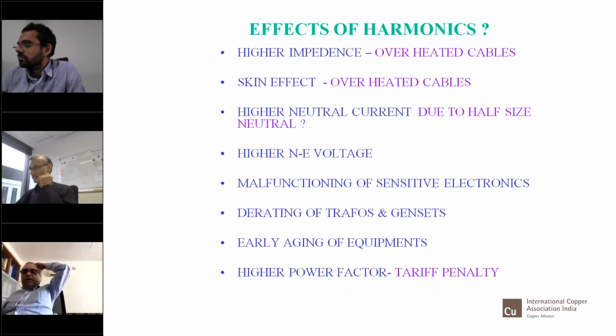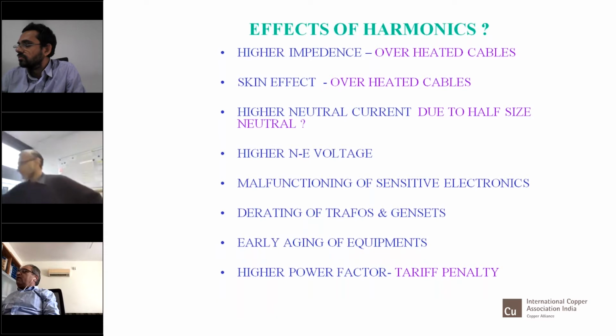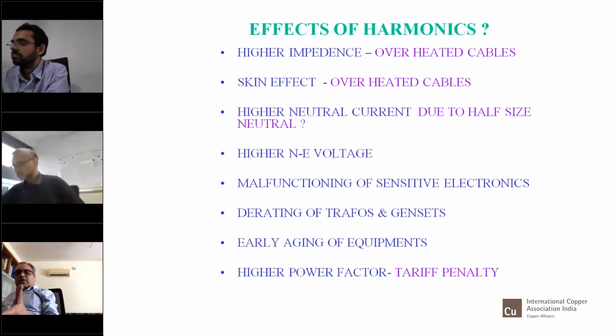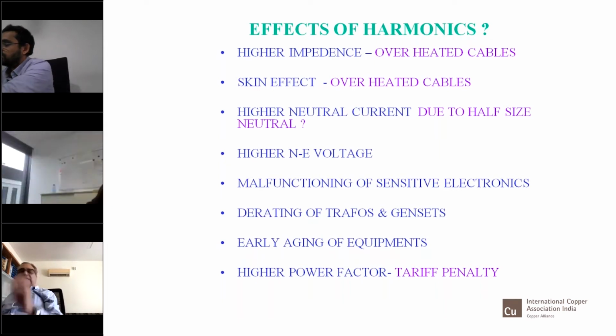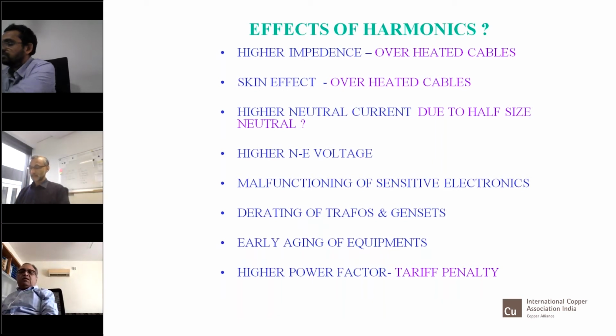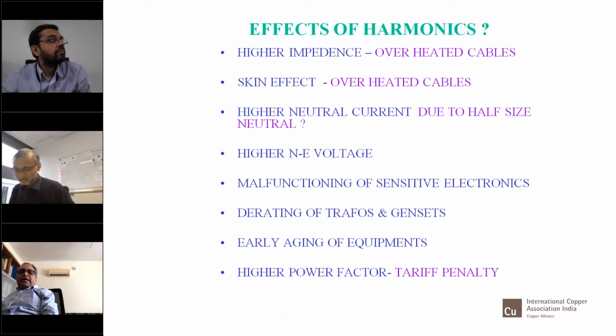Then we have higher neutral current if the frequency is 3 times, which is 150, which is what is called triplen harmonics or third harmonics. If that is prevalent, then you have a lot of neutral current because R, Y and B don't get cancelled, while for all other frequencies, including the predominant main frequency, R, Y and B cancel each other, and we have ideally zero neutral current. But when we have third harmonics, all the three phase currents get added in the neutral, especially the harmonic currents, and we have very large currents flowing in the neutral.